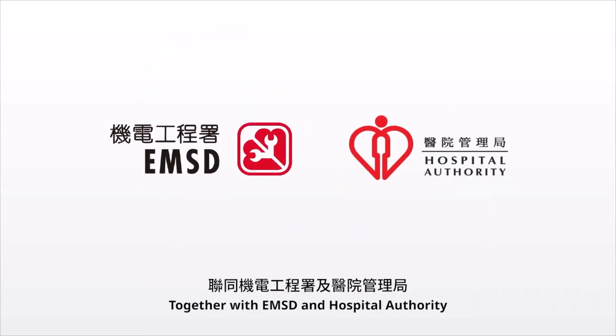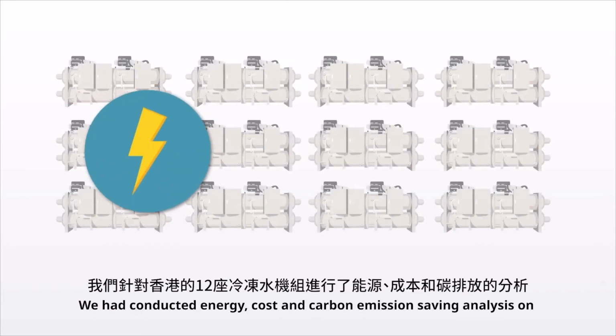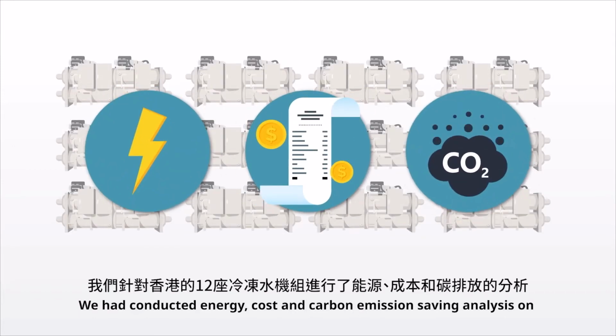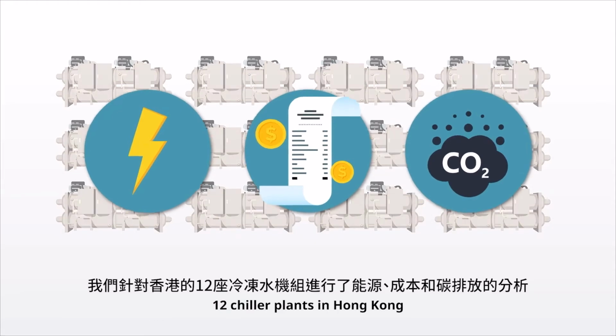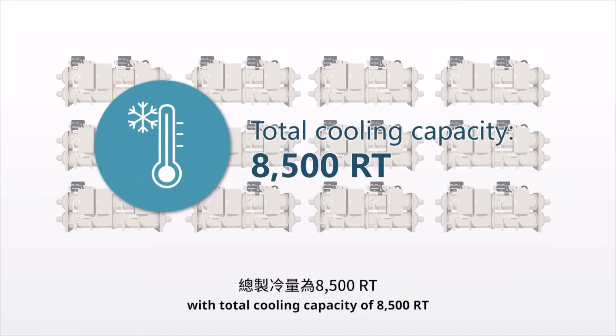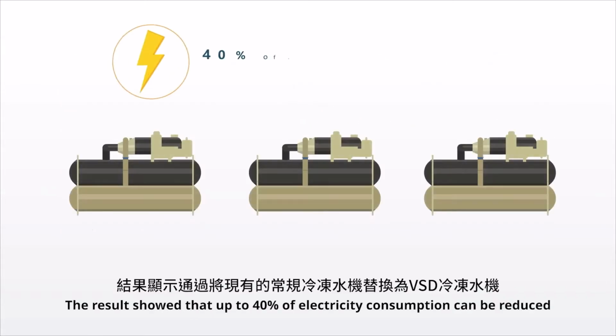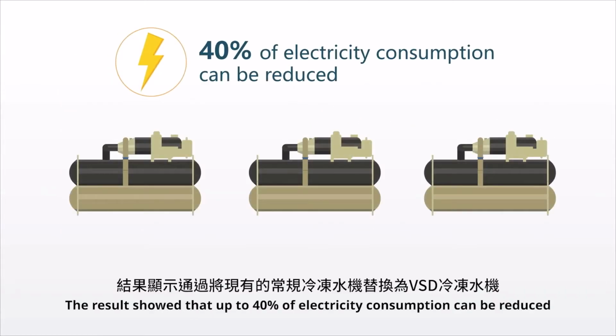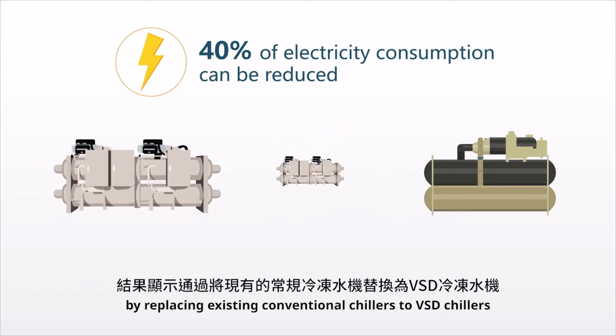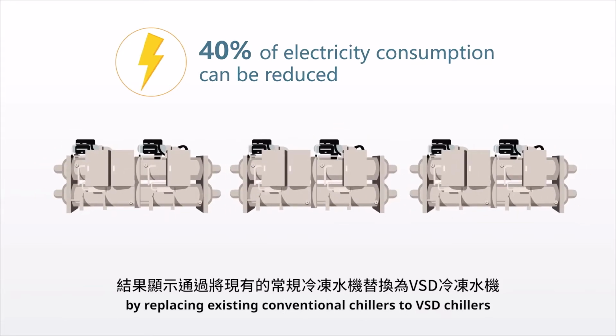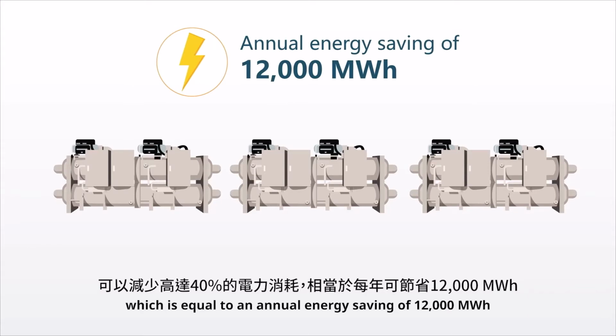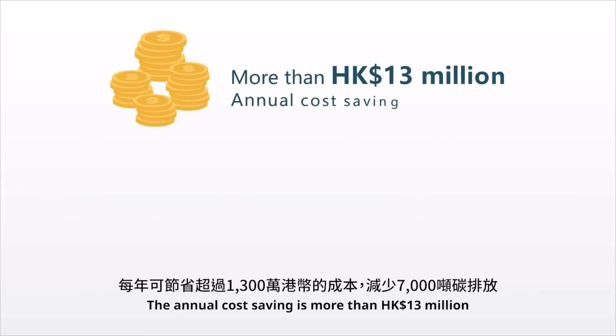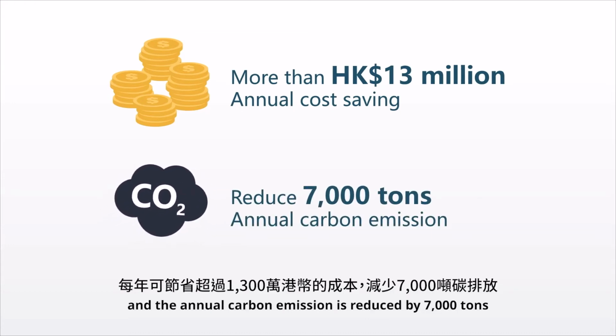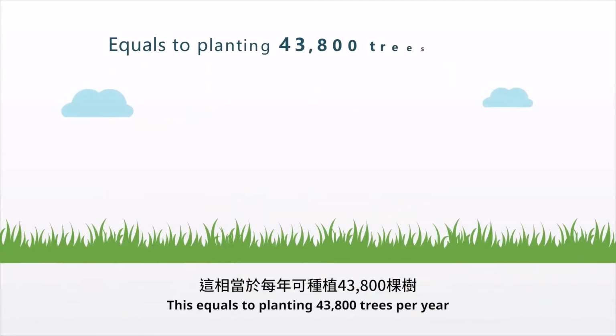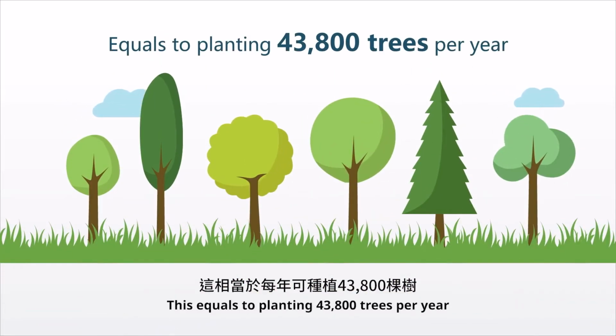Together with EMSD and Hospital Authority, we conducted energy, cost and carbon emission saving analysis on 12 chiller plants in Hong Kong with total cooling capacity of 8,500 refrigeration ton. The results showed that up to 40% of electricity consumption can be reduced by replacing existing conventional chillers with VSD chillers, which is equal to an annual energy saving of 12,000 megawatt hours. The annual cost saving is more than 13 million Hong Kong dollars, and the annual carbon emission is reduced by 7,000 tons. This equals to planting 43,800 trees per year.